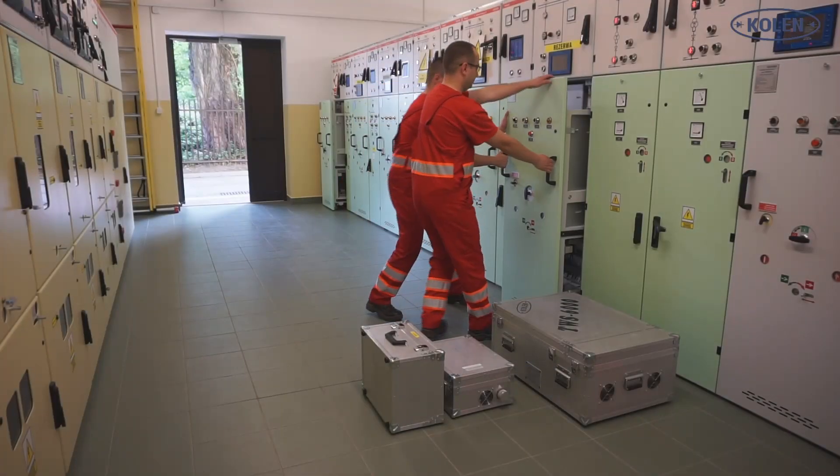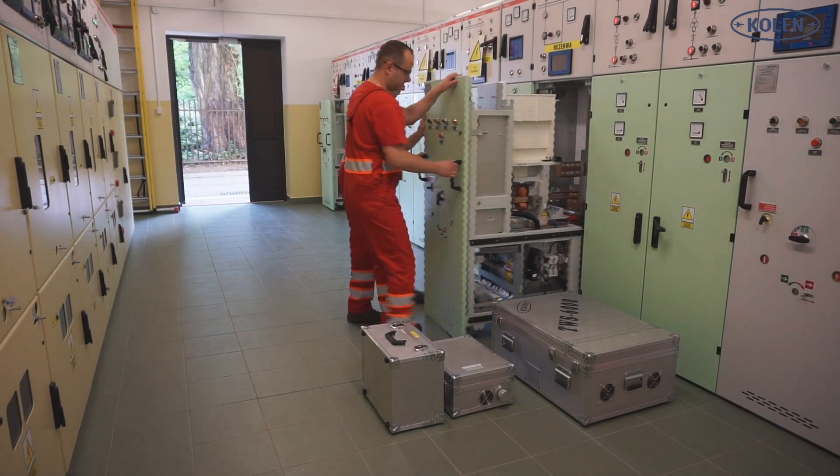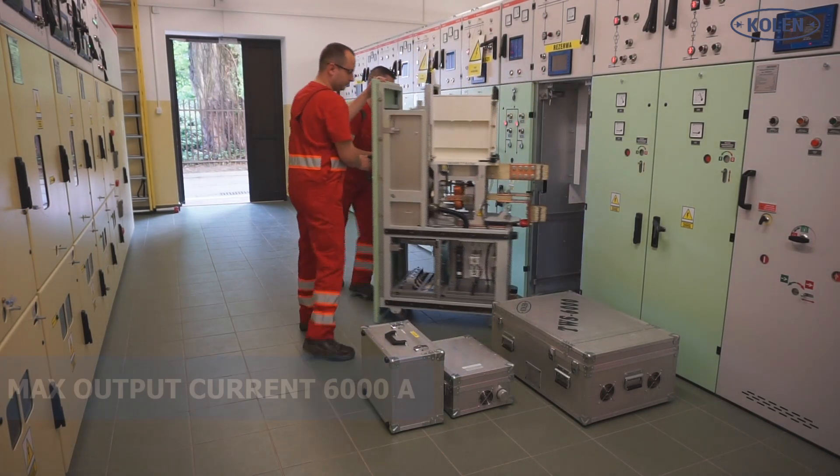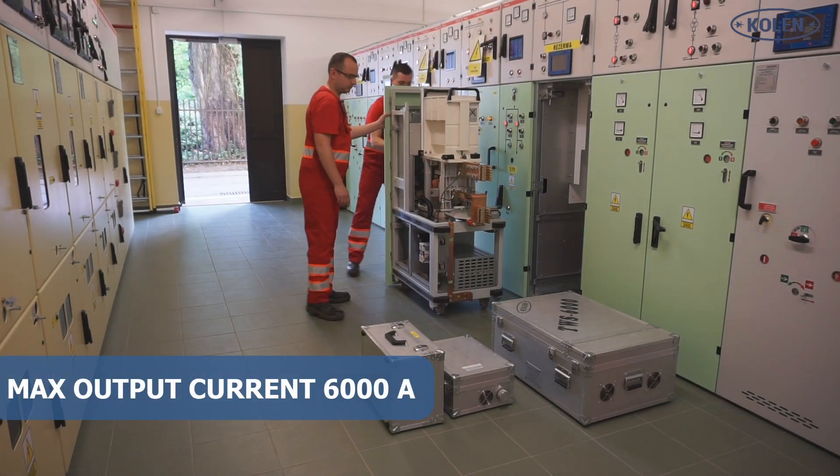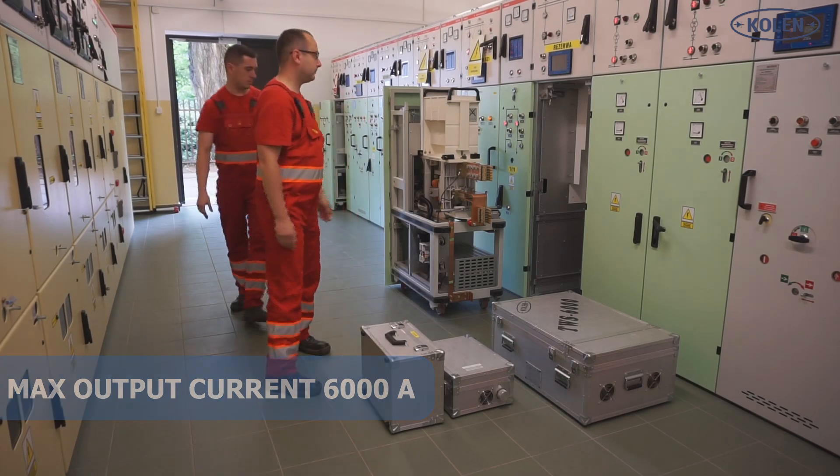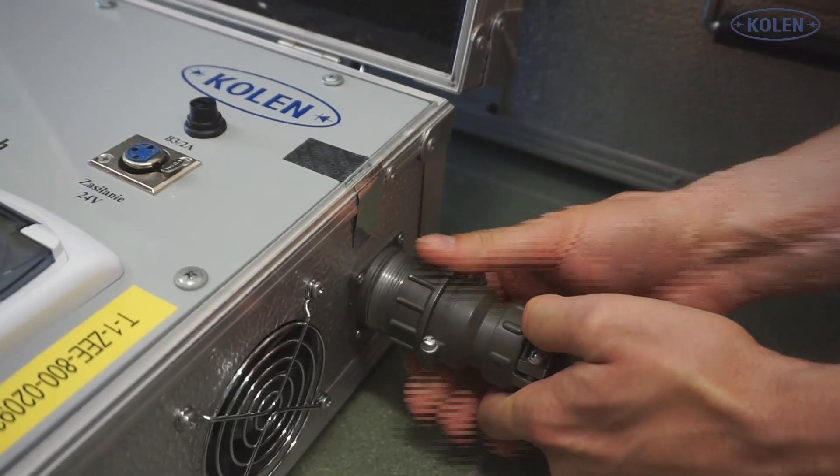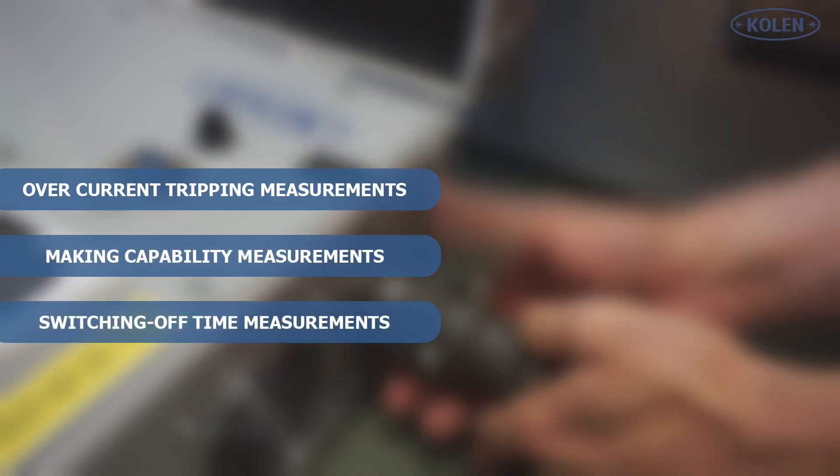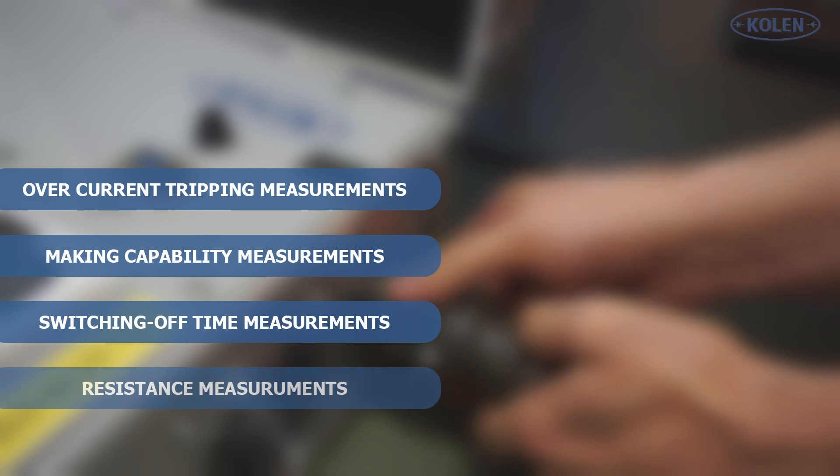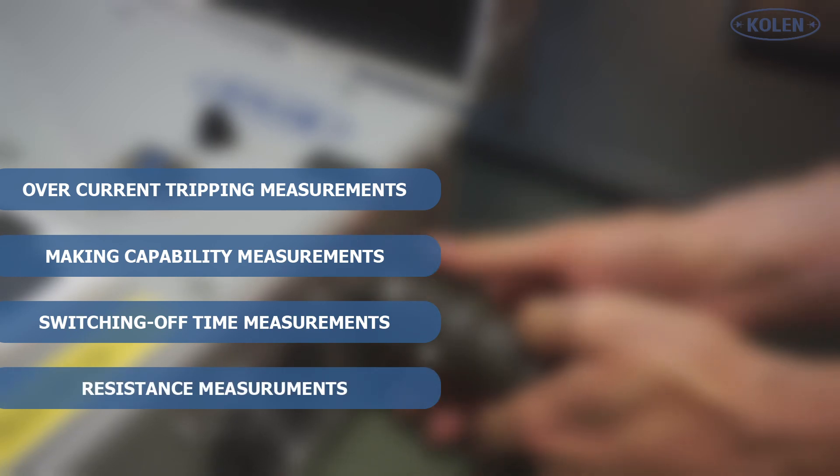Maximum output probing current of the tester is up to 6,000 Amperes. The tester TWS is capable of following HSB measurements: overcurrent tripping adjustment, making capability at a given current load, switching off dynamics, and main contact resistance.